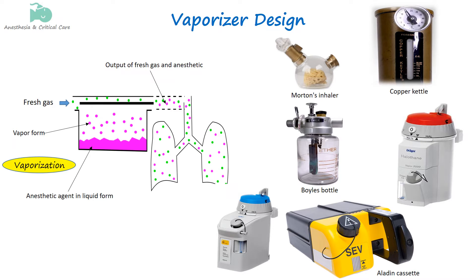The design improvements were driven by the introduction of potent inhalational anesthetics, the unique properties of some agents, a deeper understanding of their mechanisms, and the need to address issues in older vaporizers such as variations in output due to changes in temperature and pressure.